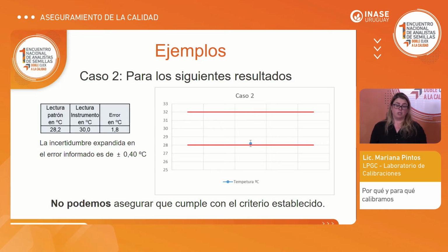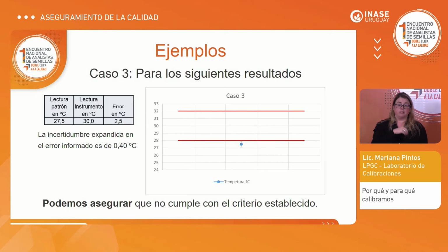Another case would be that reading the pattern, we get 28.2 with the uncertainty. It could be between 27.8 and 28.6. So if you check the graph, there is an area that is outside the control. So we cannot assure that we meet the criteria or the requirement because it can drop out. The third case, which is more extreme, is 27.5, which is outside the tolerance plus uncertainty. All the probability is outside the requirements.